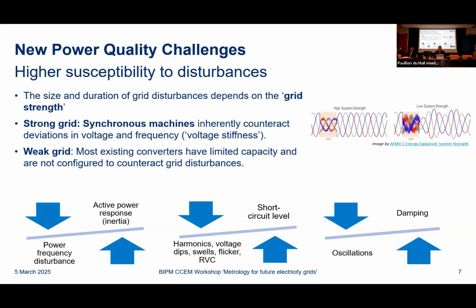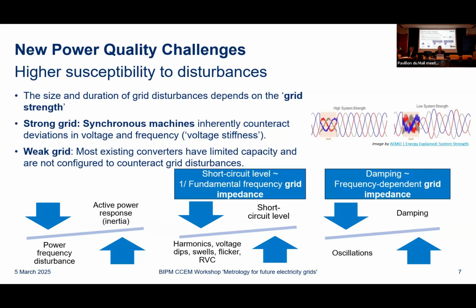So really, I think we need to not only look at the power quality side of capturing disturbances, but also start to look at things a bit more holistically or in an interconnected way related to this grid strength characterization. On the topic of grid strength, if we look at the short circuit level and the damping, it's worth noting that in terms of the actual property in the grid itself, that's very much related to the grid impedance. So I'm also going to touch on some of the measurement challenges associated with that.